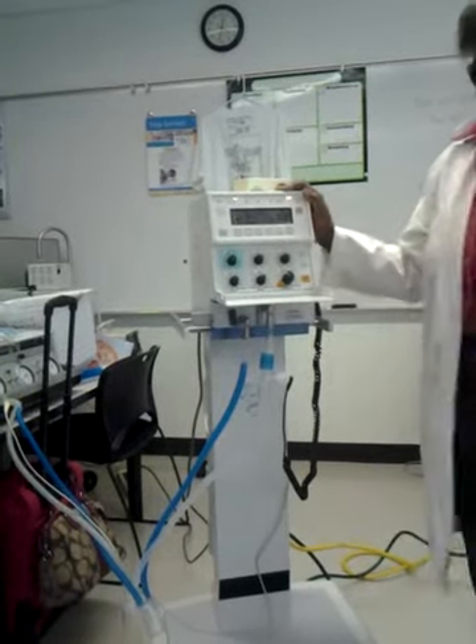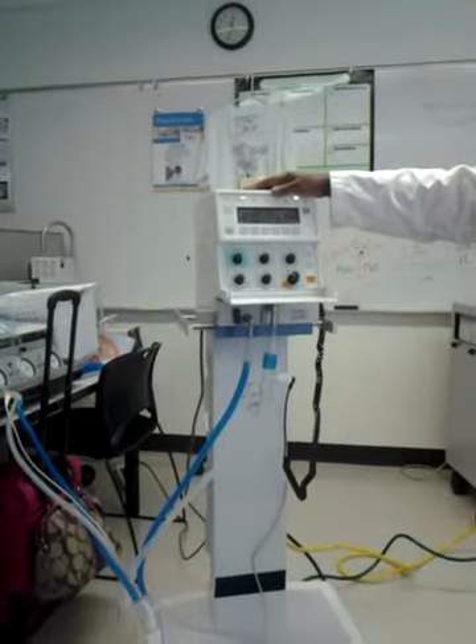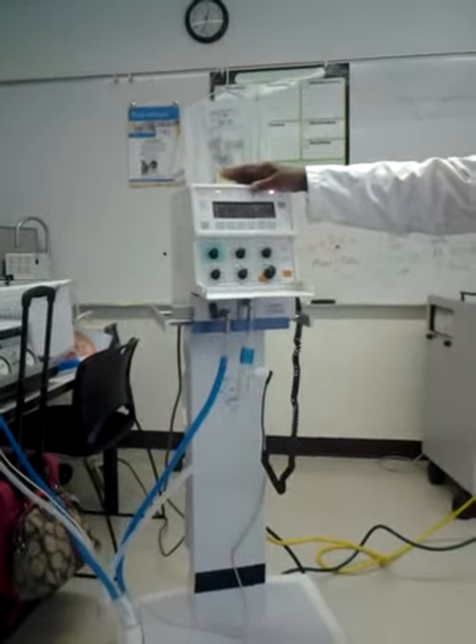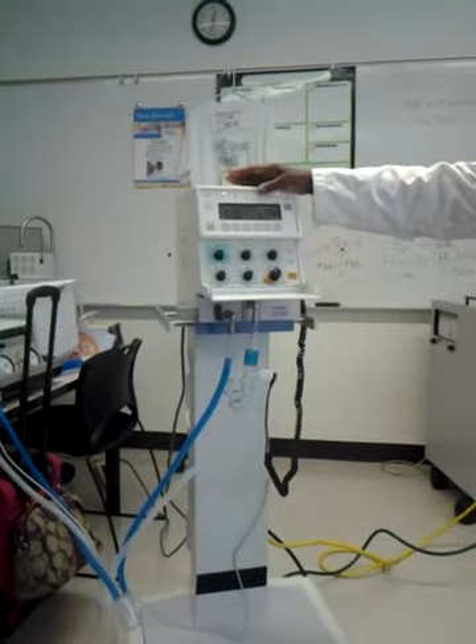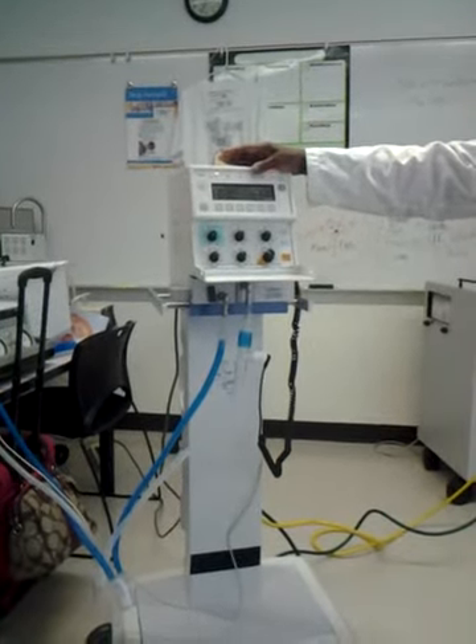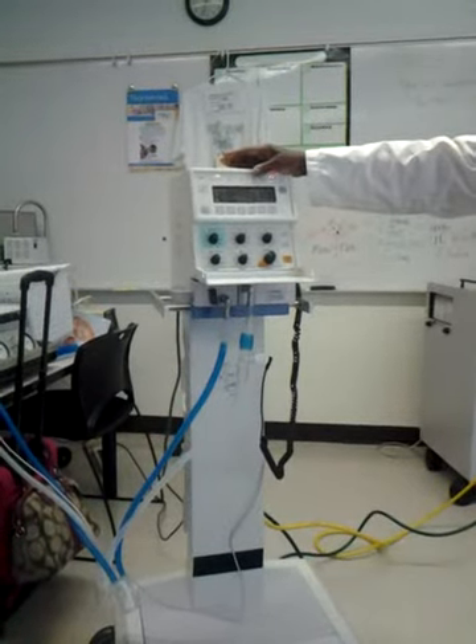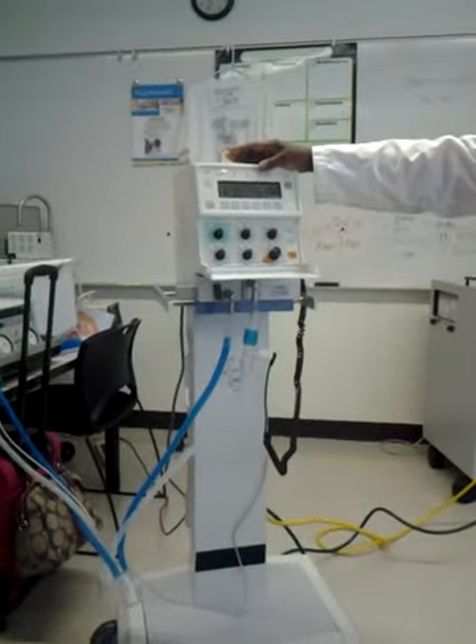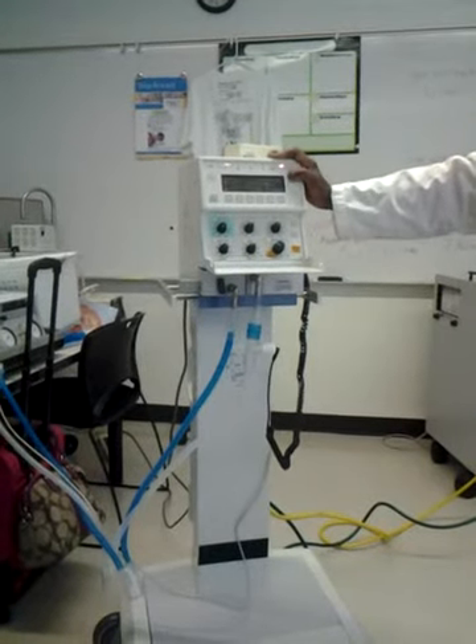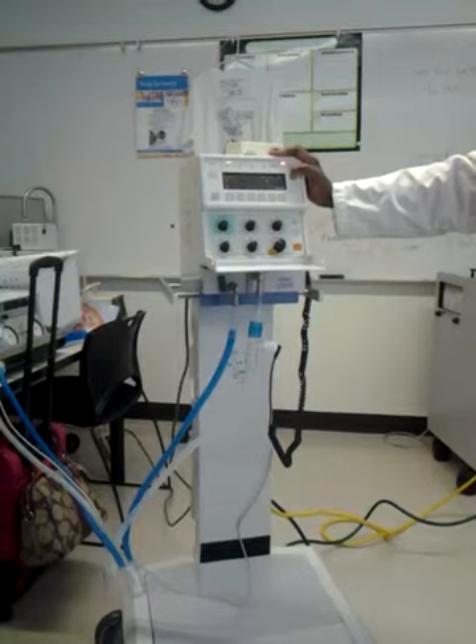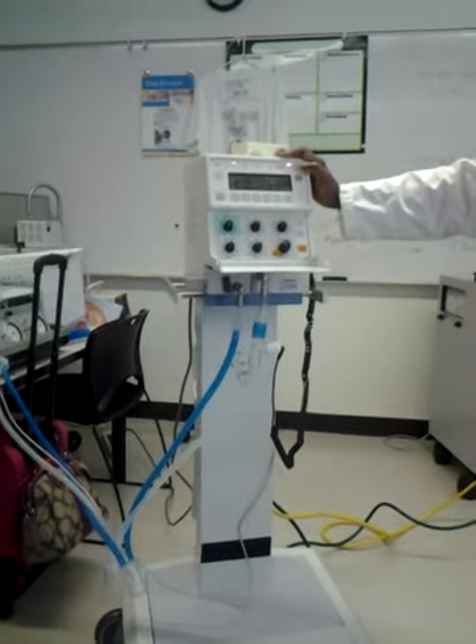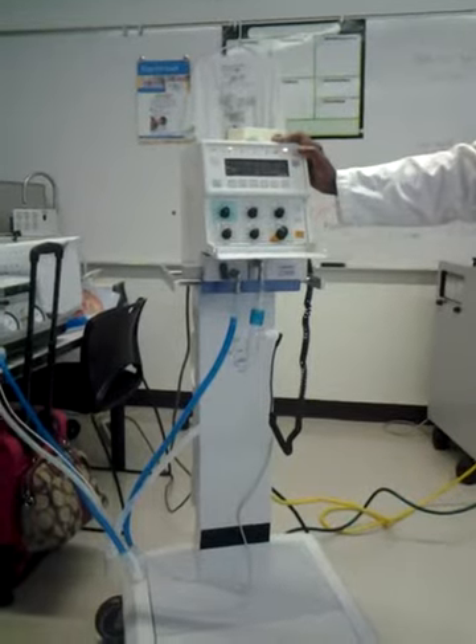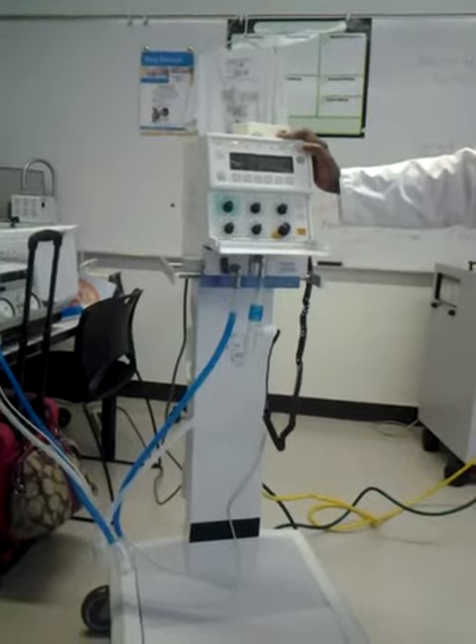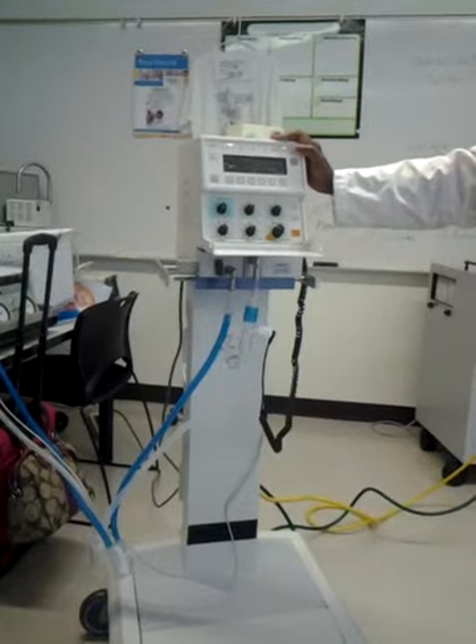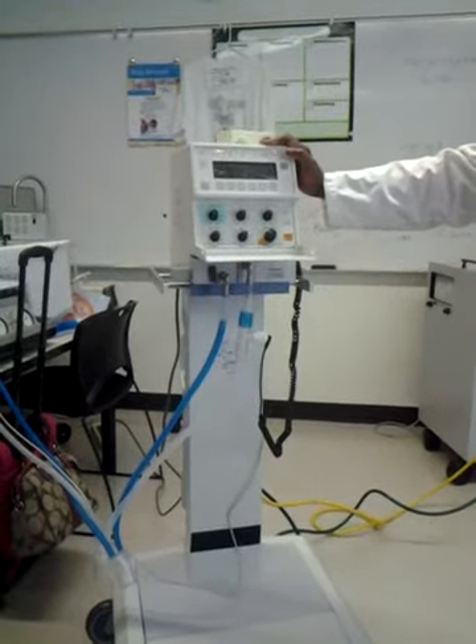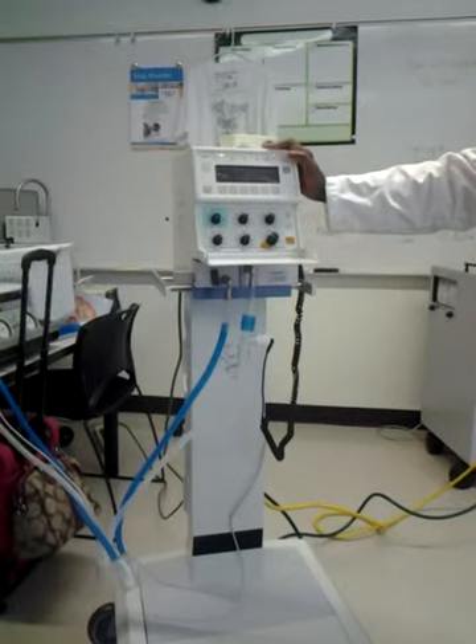So with adults we normally set 10 or 20 above and 10 or 20 below? You don't set 20 here; you're going to set it at 5 to 10. On these ventilators, if you set the alarm pressure, they can get up to that pressure that you're setting the alarm at, so you don't want more than 10 above. You don't want it that far above, because if the baby gets a kink or a plug, you want to know that right away. You don't want it set so high that it's not going to alarm right away. So you want 5 to 10, not more than 10. With the adult, we tell you 15, 20 above. With the child, it's going to be more like 5 to 10.